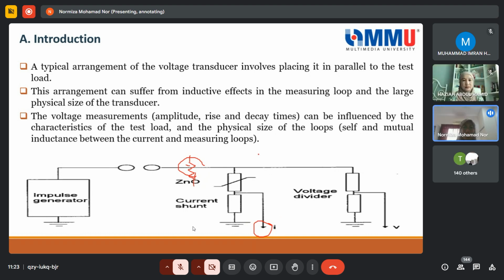And we know the maximum voltage that can be measured, because the oscilloscope is in voltage, not in current, is 50 volt. So the maximum voltage to be measured is 50 volt. For example, you apply 100 kV to the zinc oxide arrester, which is of course non-linear, but for example the resistance is 1 kilo-ohm, so the current should be 100 amp, right? 100 amp.